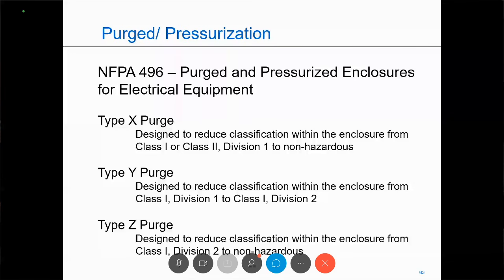And the reason for that is this would be like putting an everyday general purpose rated switch inside a Class 1 Division 1 area. If you lost the purge, it would be no different than putting a NEMA 1 safety switch inside that area. So that's why it's imperative that when you lose the purge, all the electrical equipment shuts down.